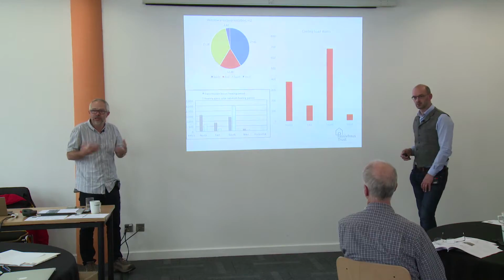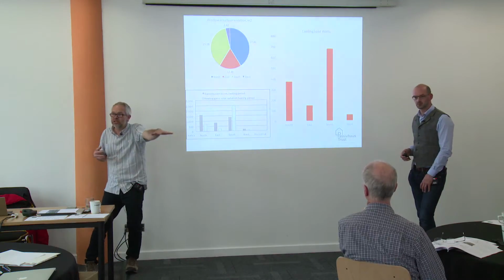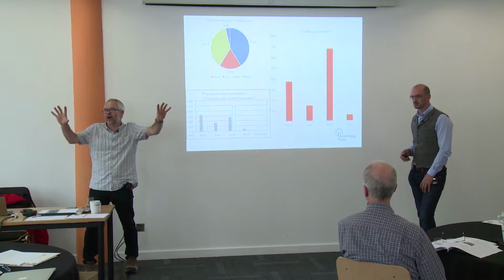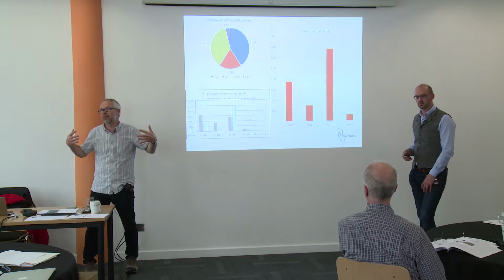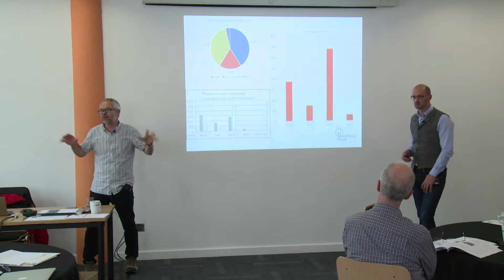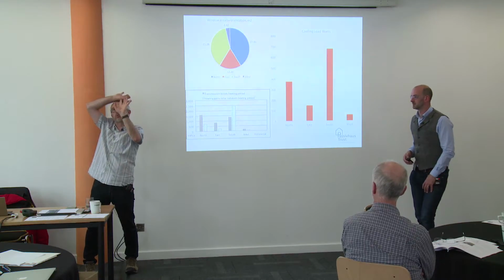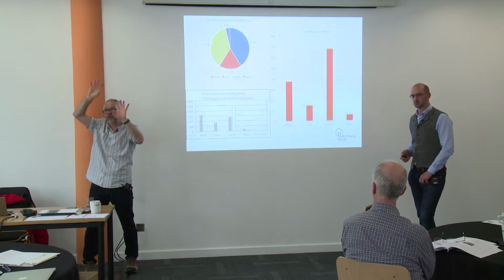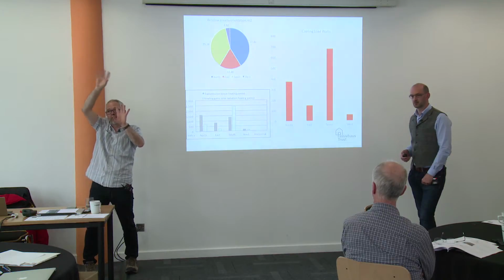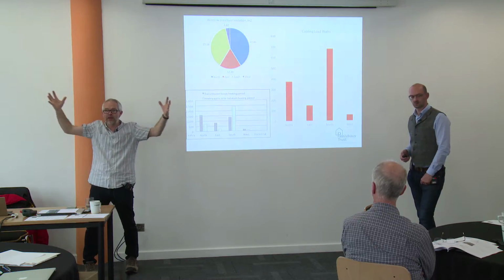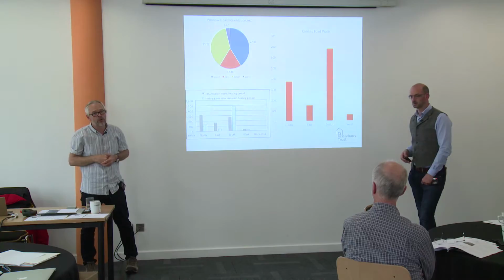So, counterintuitive. It's partly the afternoon sun does come round, but it's also just the bright sky. There is solar gain in summer, even from the north. And if you've got a lot of glass, it will contribute. And same with north skylights. Well, much worse with north skylights, because again, people say, oh, it's north, it'll be fine. Afternoon sun in summer will come over. So if you put a big skylight on the north, it will cook you.